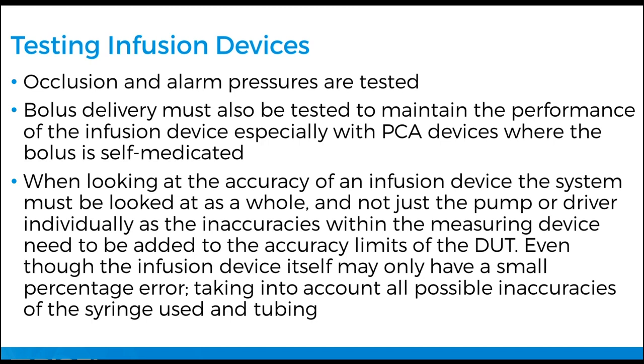When looking at the accuracy of an infusion system, it must be looked at as a whole, as a full system, not just the pump and the driver individually, because inaccuracies can happen within the measuring device. This can be small percentage errors with the syringe that's used, the tube might have a kink in, air bubbles, this type of thing.